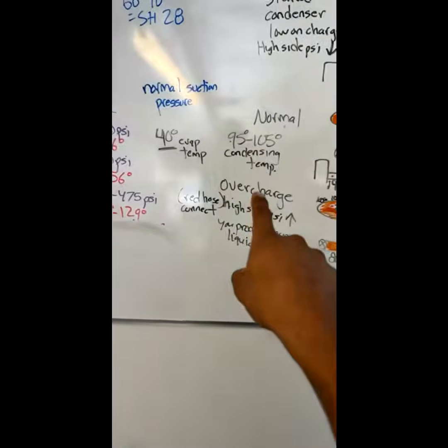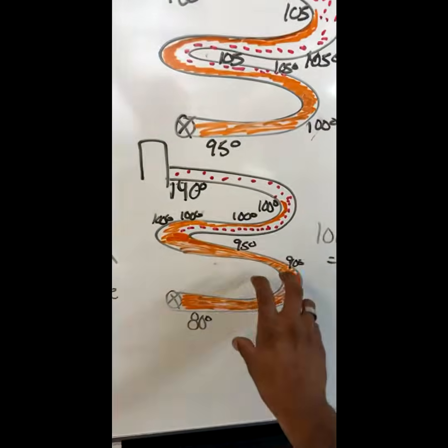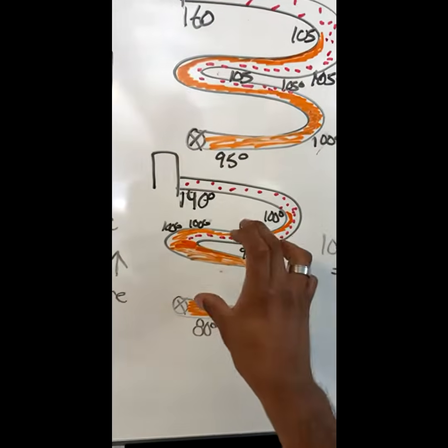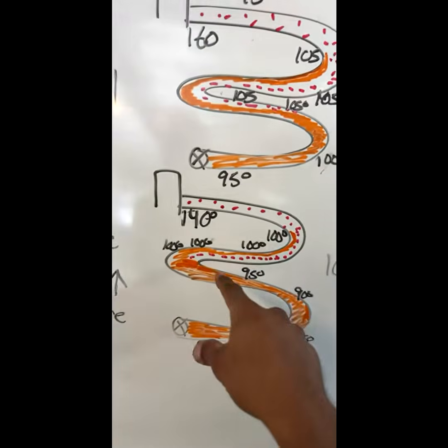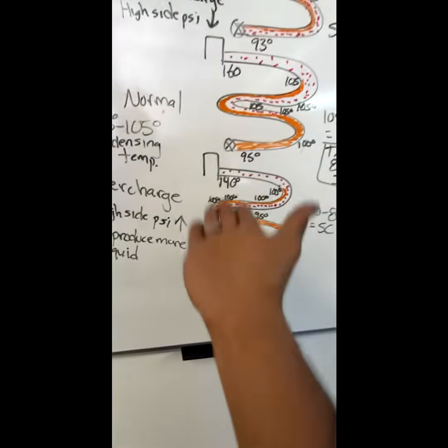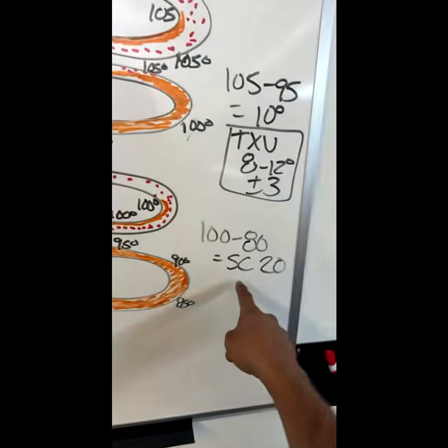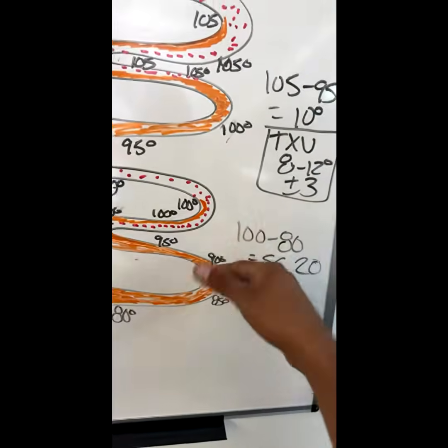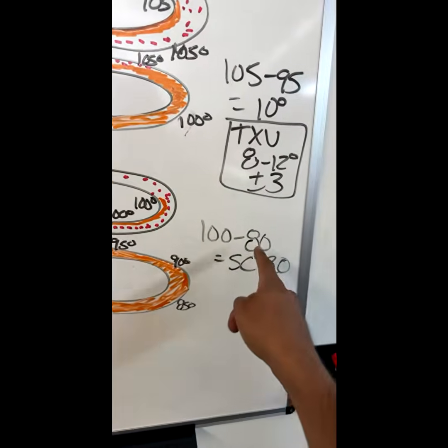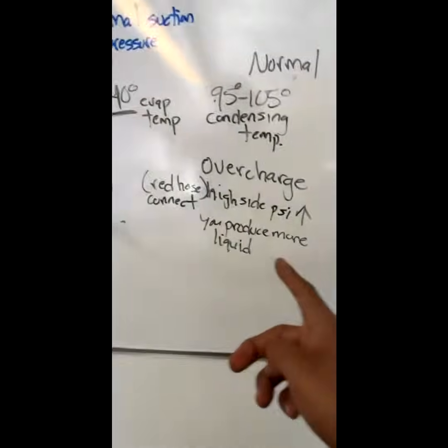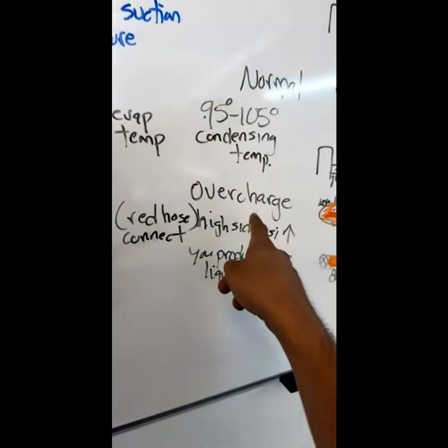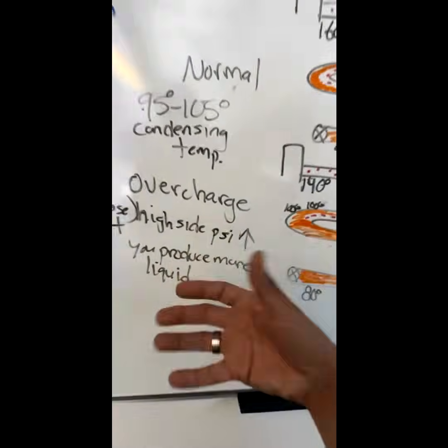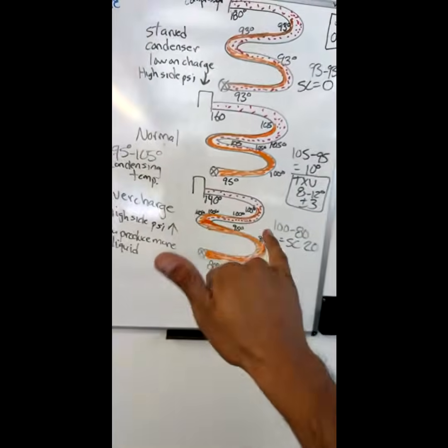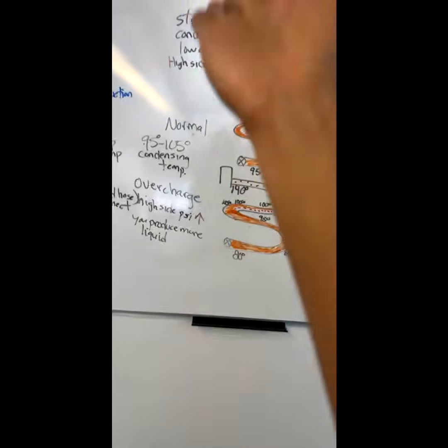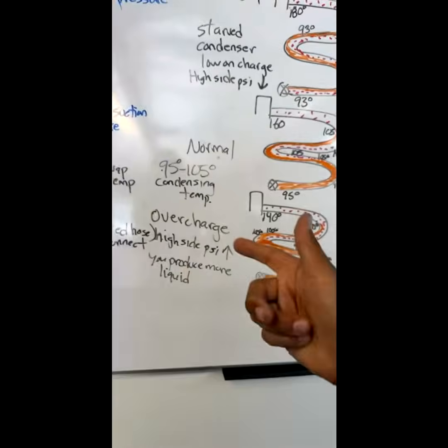And then when a system is overcharged, you got so much liquid, it's actually taking up space in that condenser coil. So then that runs a higher head pressure, and then you end up with a high subcool. And these are just numbers, just an example: 100 minus 80, subcool of 20. So with an overcharged system, you're producing more liquid because there's more heat rejection, but your condensing temperature is too high, and your compression ratio goes up.